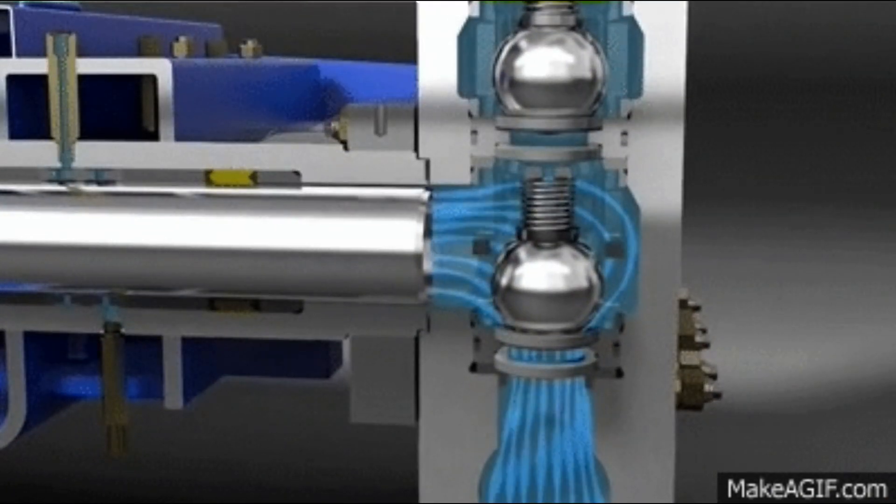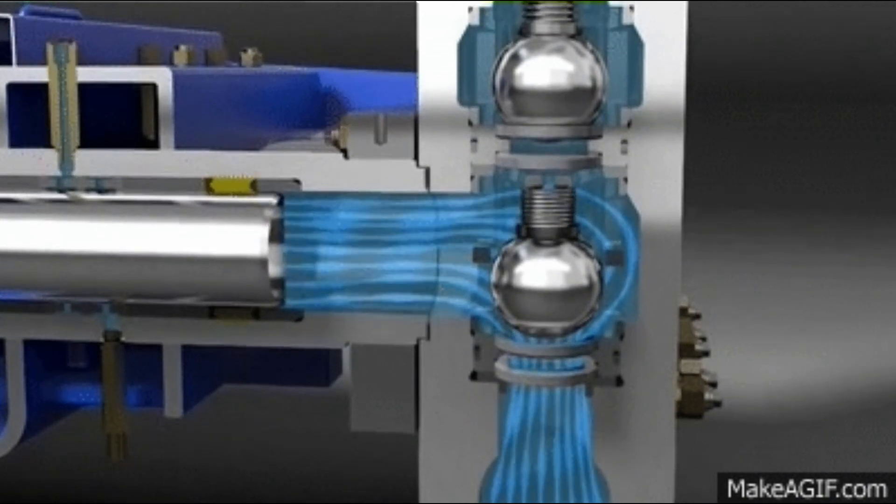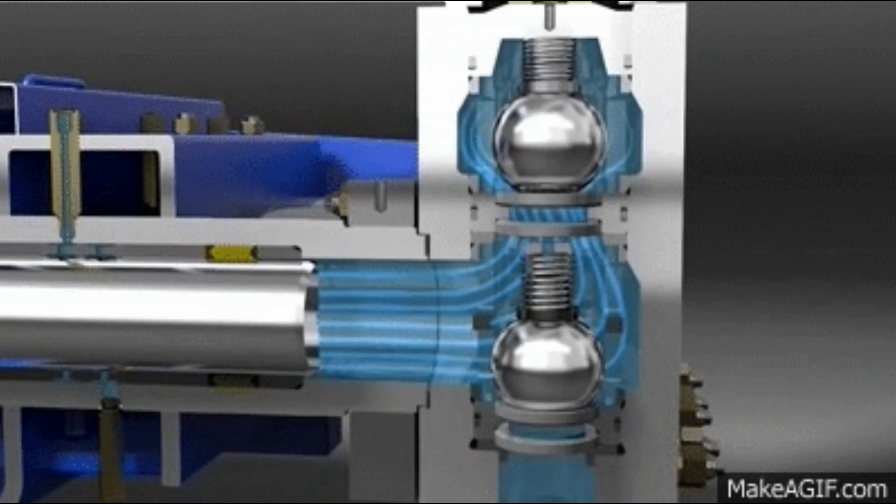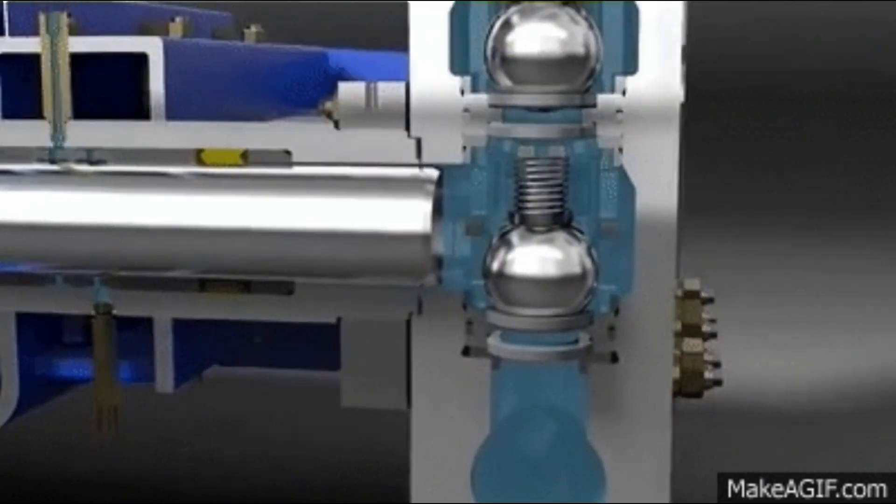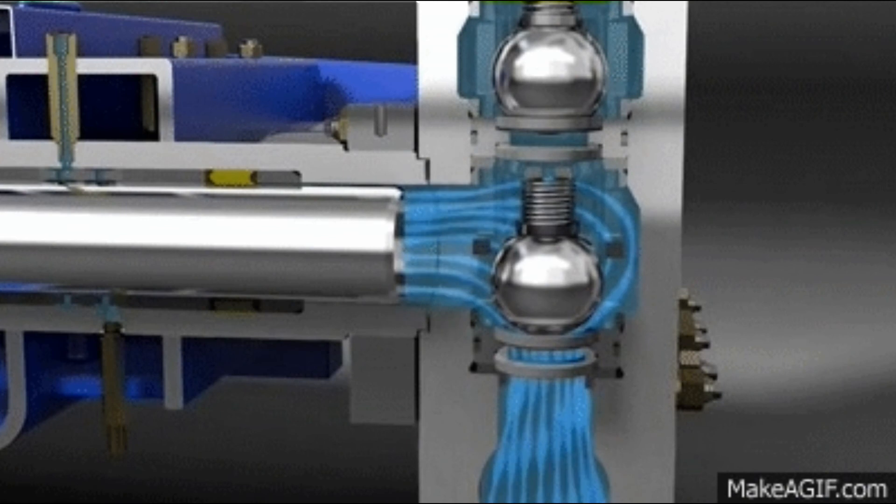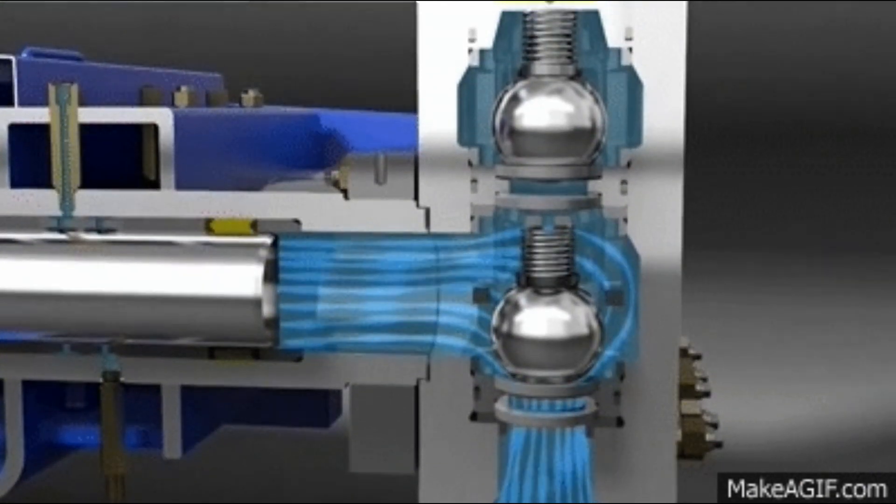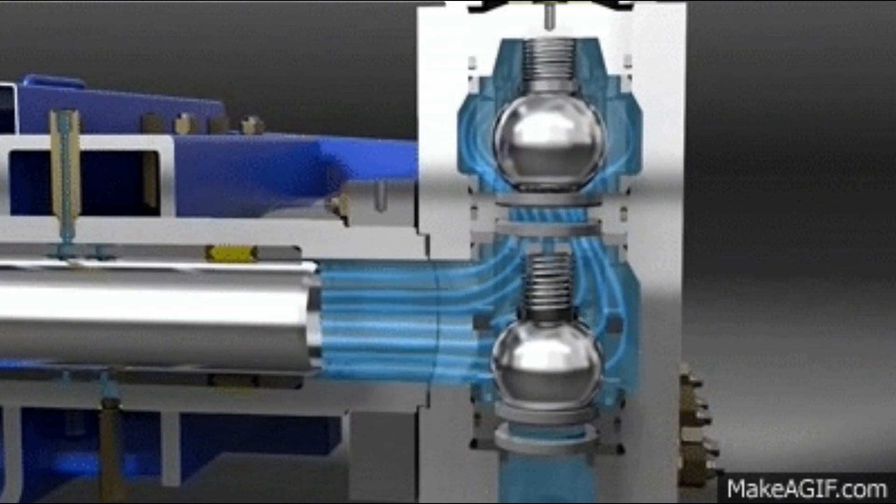In the forward stroke the plunger pushes liquid out of the discharge valve. A common problem with only one cylinder in plunger pumps is that the fluid flow varies between maximum flow when the plunger moves through the middle positions and zero flow when the plunger is at the end positions. A lot of energy is wasted when the fluid is accelerated in the piping system. Vibration and water hammer may be serious problems. In general these problems are compensated for by using two or more cylinders not working in phase with each other.